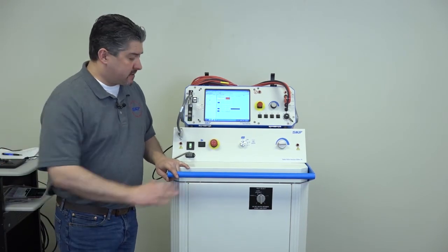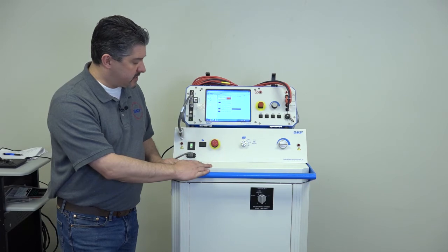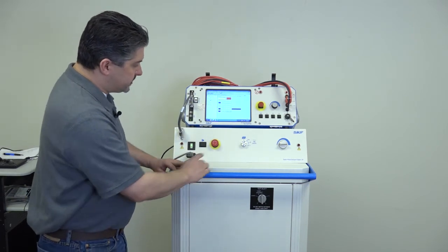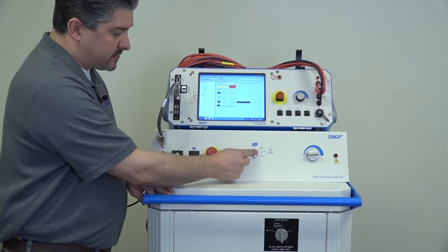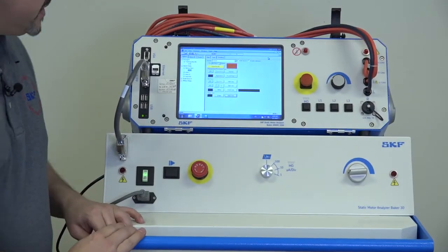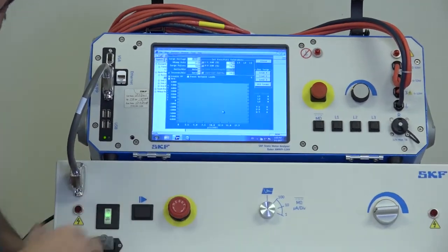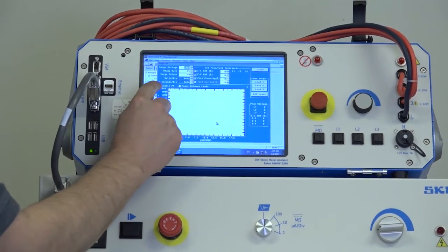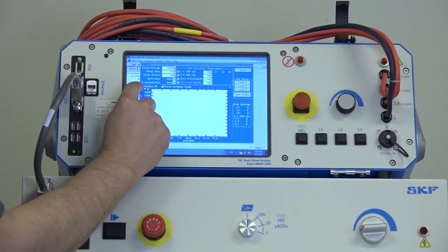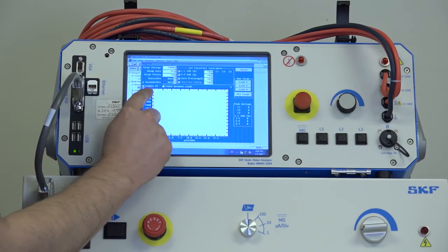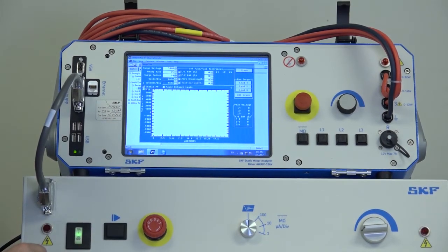Now we're going to demonstrate the use of the power pack to surge test a motor winding. The first thing we want to do is ensure our function selector switch is in the surge test position at 12 o'clock. Once that's been verified, we're going to go into the software setup screen for surge testing and check the enable power pack checkbox. Make sure your test voltage is set appropriately, which you want.